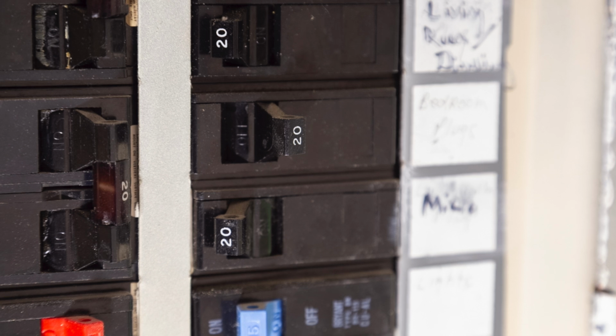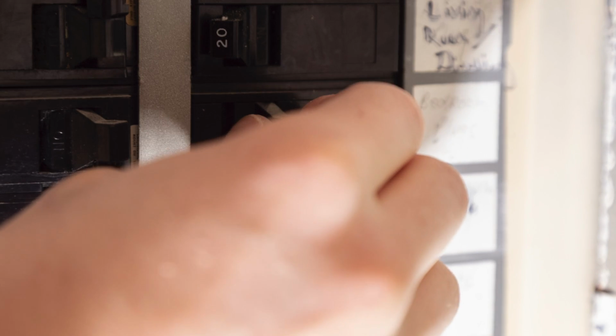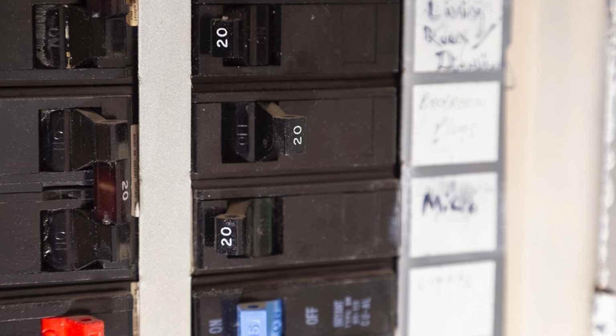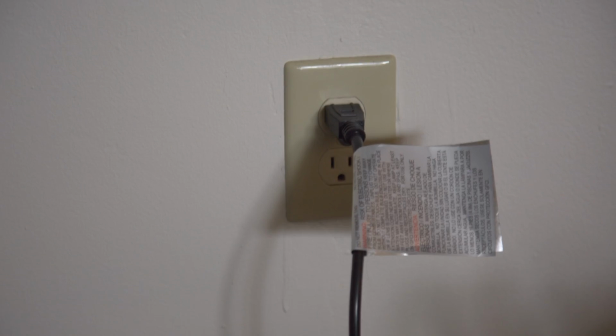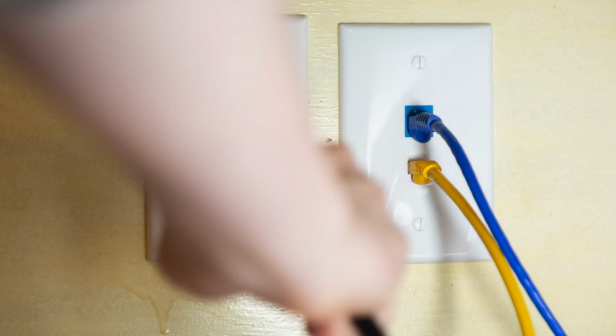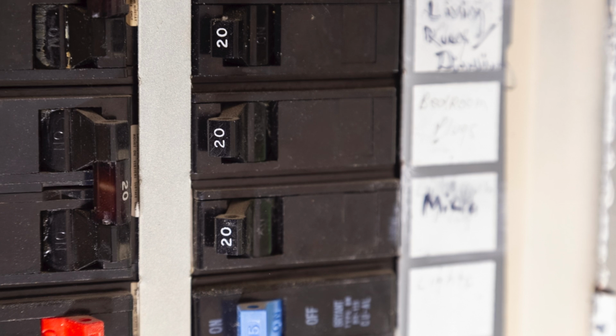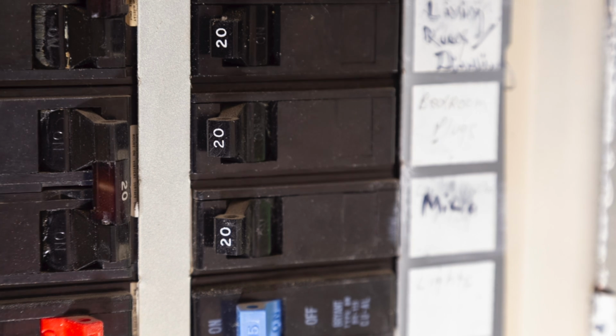First, verify the short by resetting the breaker. If the breaker immediately trips upon resetting, a short is the likely cause. Check over the cords of any device downstream from the tripped breaker for melted plastic insulation or exposed wires. These are likely causes for short circuits. If you remove the device, turn the breaker back on, and after waiting a time it does not trip, the device is most probably the cause of the short.